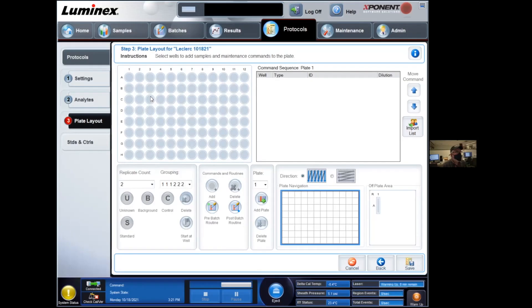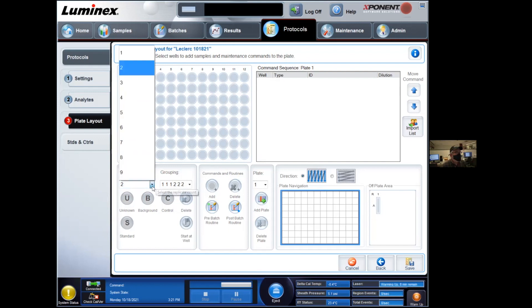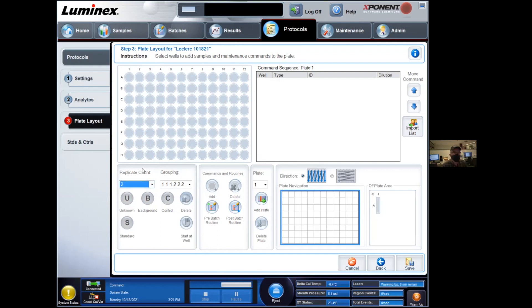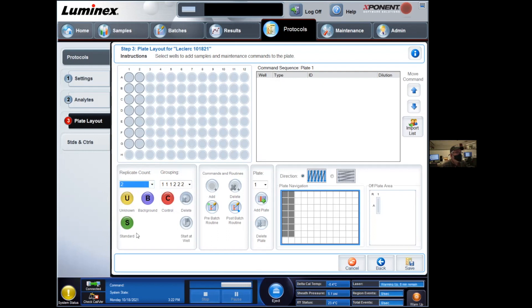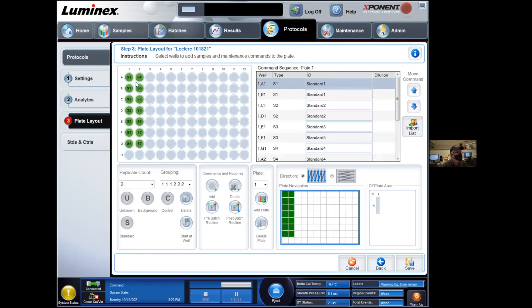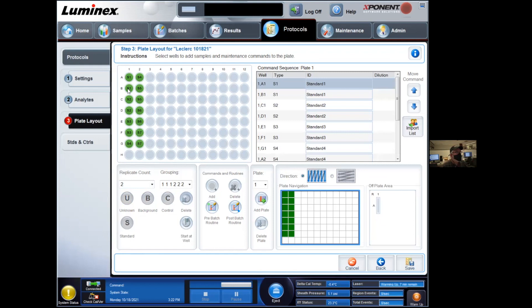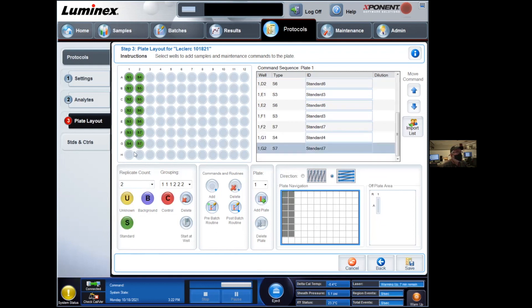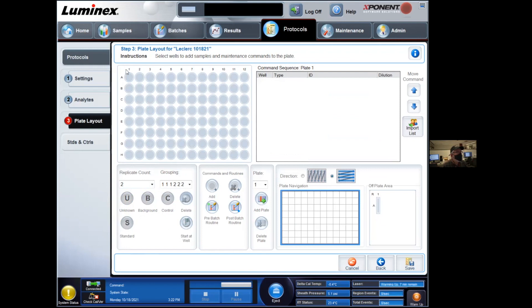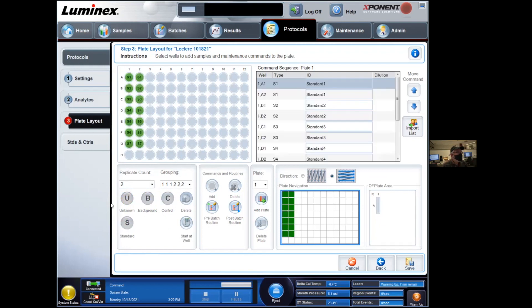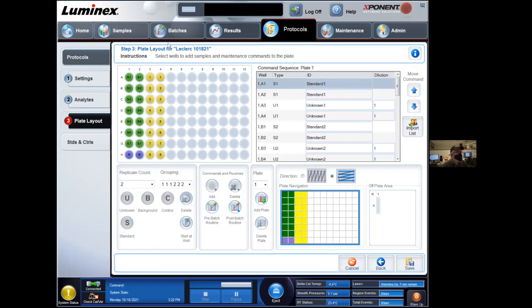Next up, we are going to set up the layout on your plate, and we have a bunch of tools at the bottom. The replicate count tells us how many copies of the same samples you are running on this plate. In general, we prefer duplicates for each of these standards and controls. You are simply going to select the wells for any standard samples, the background and controls, and then click on the type of wells that we're looking for. S1 on A1, B1, S2 on C1, D1, and so on. And this is a function of the direction of the plate over here. If I did S1 on A1, A2, and standard 2 on B1, B2, and so on, I want to change this orientation. And so now I can make a correction by selecting these wells, removing them, and adding them right back.